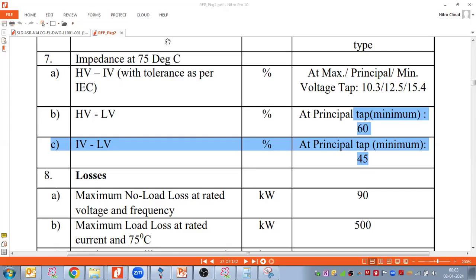And one more thing, you told that in the UK they are using YD1 and that zigzag earthing transformer for earthing. What is the advantage in that, sir? A similar arrangement we also used in Qatar. They used a YD transformer, a 32 or 40 MVA transformer, and after that they put the earthing transformer. Nowadays they are not using it.